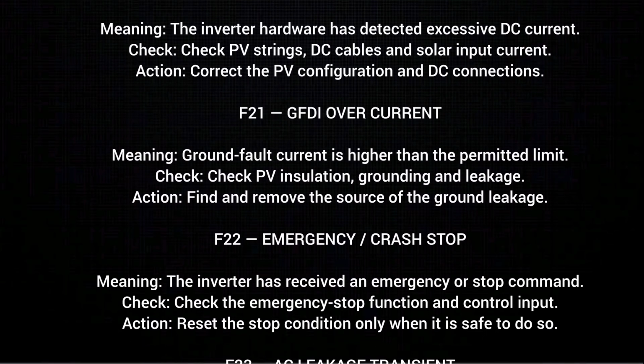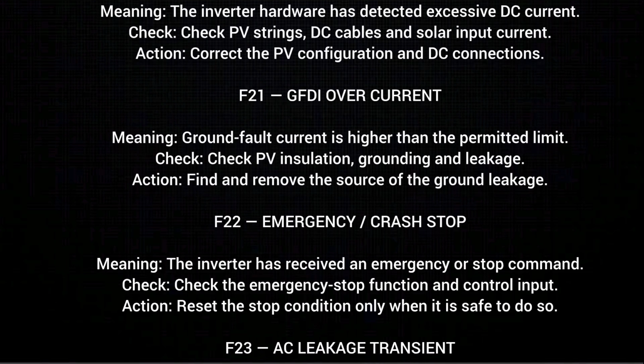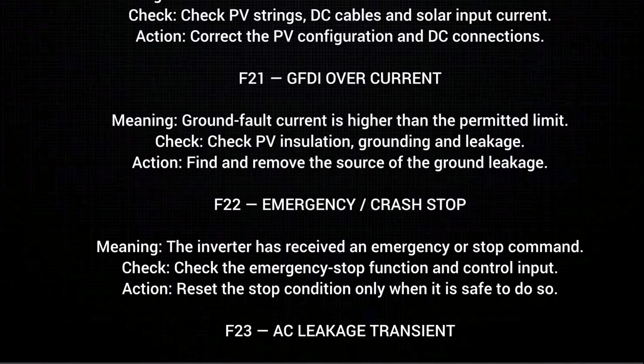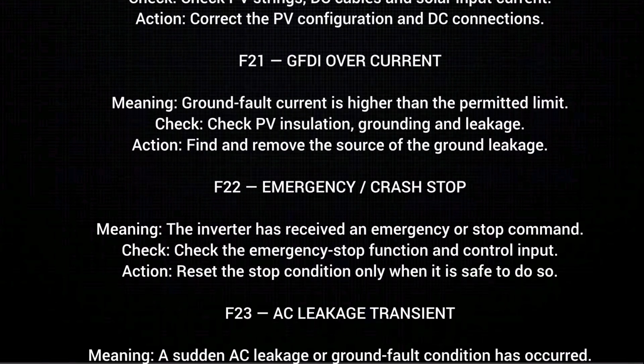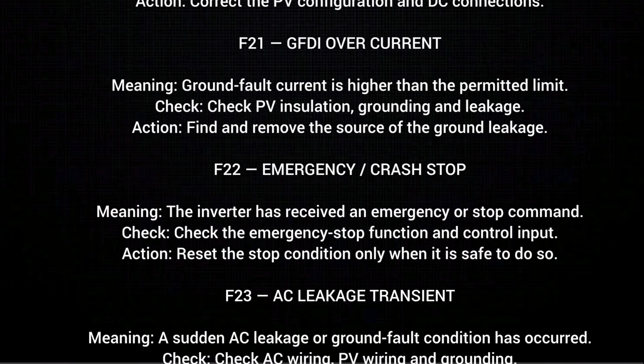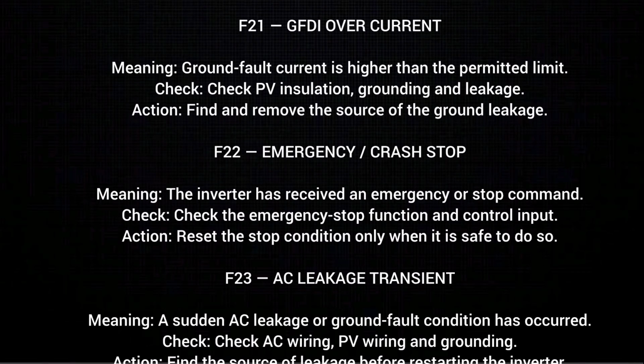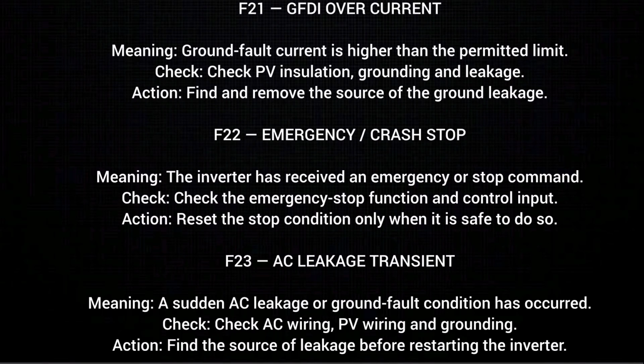F21 GFDI overcurrent, meaning ground fault current is higher than the permitted limit. Check. Check PV insulation, grounding and leakage. Action. Find and remove the source of the ground leakage.